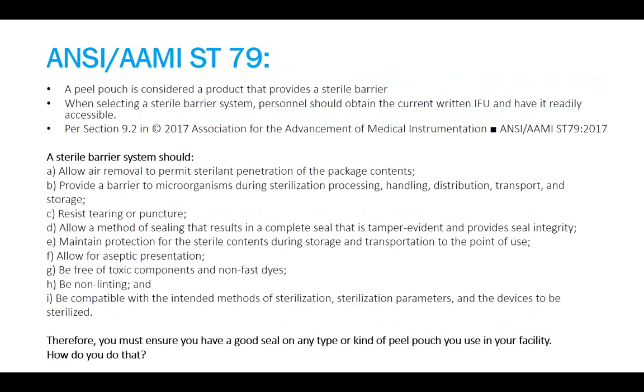So we've started building the case for why you must verify. Again, quoting from AAMI's ST79 — I can only take part of it, can't take all of it, so make sure you have those standards in your department — a pouch is considered a product that provides a sterile barrier. When selecting a sterile barrier system, people should obtain the current written IFU from the manufacturer and have it readily accessible. One section to go to is 9.2, which talks about what a sterile barrier should be and what you should look at.